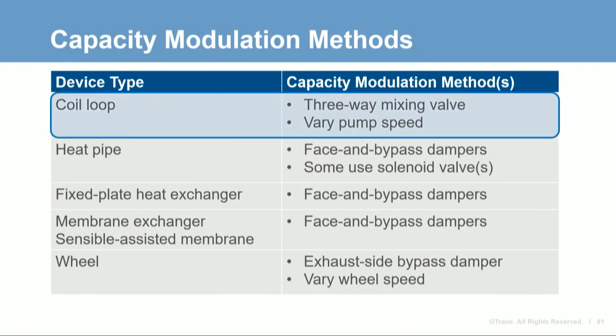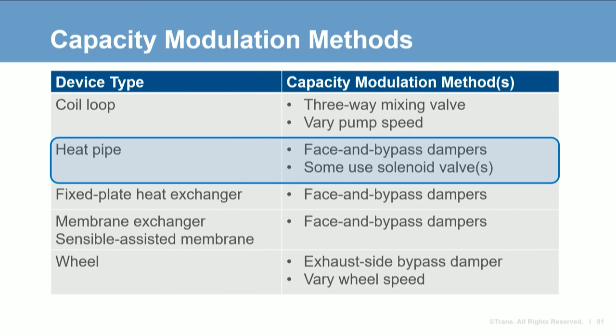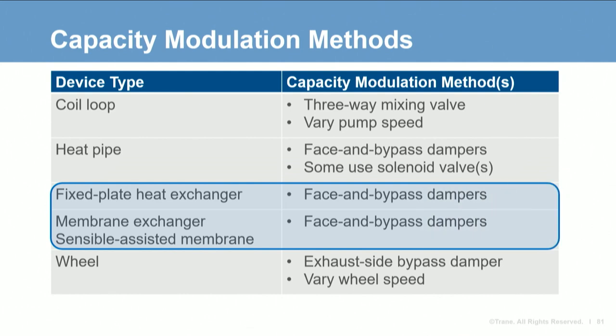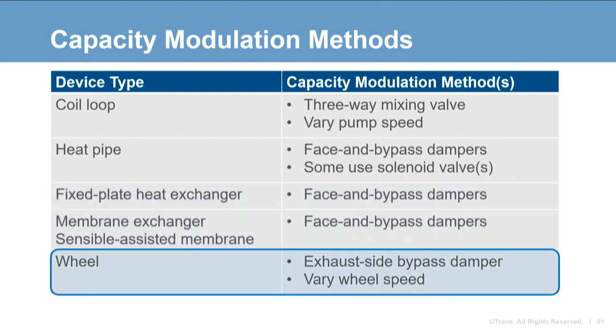Many coil loops use a three-way valve to reduce the flow rate through the supply side coil when less heat transfer is desired. Alternatively, a variable speed pump can reduce fluid flow rate and heat transfer. Heat pipes use face and bypass dampers or multiple integral solenoid valves to reduce capacity. Fixed plate heat exchangers modulate their face and bypass dampers to vary the amount of heat transferred. Membrane exchangers also use face and bypass dampers. For a wheel, TRANE recommends modulating the exhaust side bypass damper rather than varying the rotational speed. A white paper explaining this recommendation is included in the bibliography.